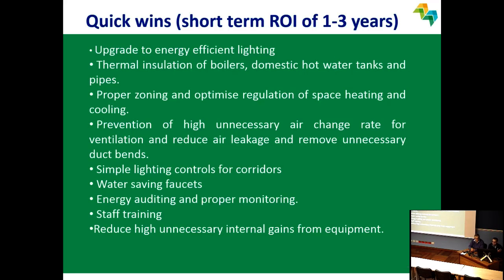Short-term return on investment of 1 to 3 years: one should upgrade to energy efficient lighting, insulate boilers, domestic hot water tanks and pipes, properly zone and optimize circulation of space heating and cooling, and prevent high unnecessary change rate for ventilation, reducing air leakage and removing unnecessary duct bends.